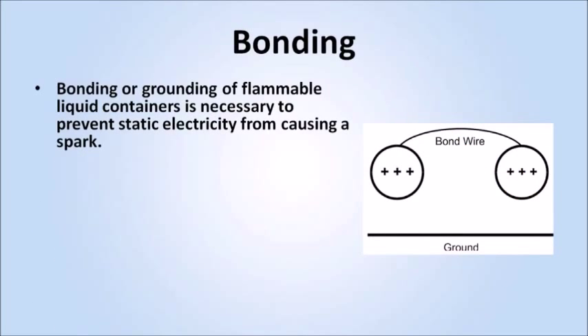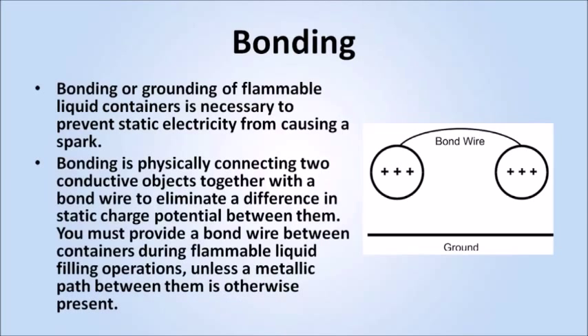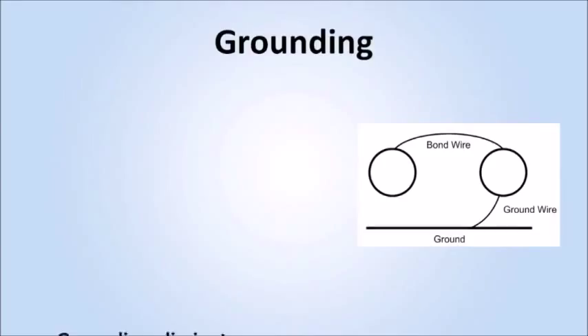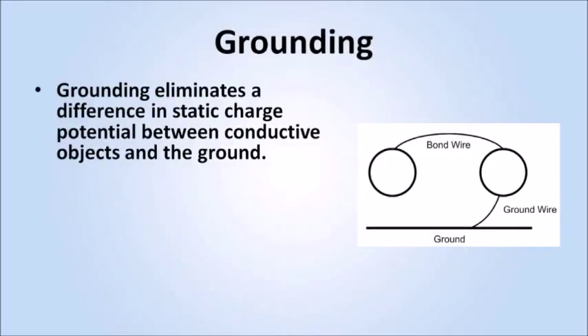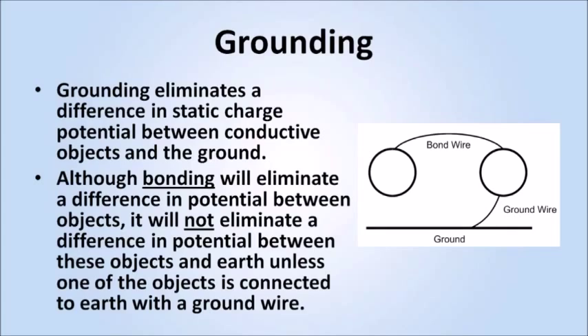Bonding or grounding of flammable liquid containers is necessary to prevent static electricity from causing a spark. Bonding is physically connecting two conductive objects together with a bond wire to eliminate a difference in static charge potential between them. You must provide a bond wire between containers during flammable liquid filling operations, unless a metallic path between them is otherwise present. Grounding eliminates a difference in static charge potential between conductive objects and the ground. Although bonding will eliminate a difference in potential between objects, it will not eliminate a difference in potential between these objects and Earth, unless one of the objects is connected to Earth with a ground wire.